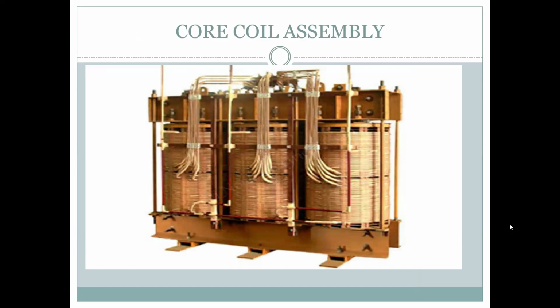transformer insulation. We'll be coming to that, but here I just touch upon it. The transformer is the poorest of the poor; the lowest grade of insulation is used in a transformer. That is classified as A, B, F, H, C. These are the different insulation levels. Of all equipment, the transformer has the lowest grade of insulation, that is Class A insulation.